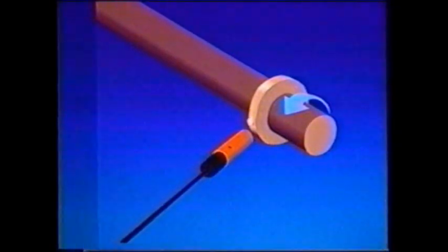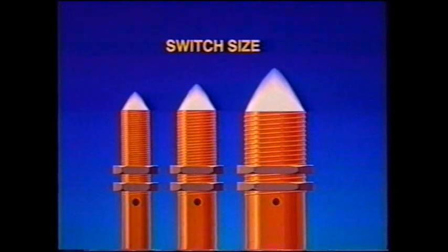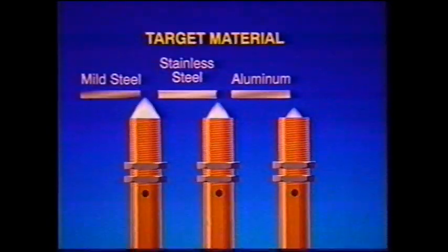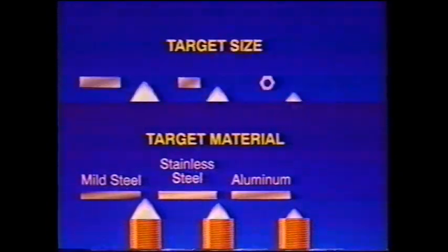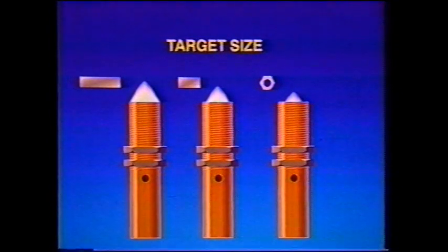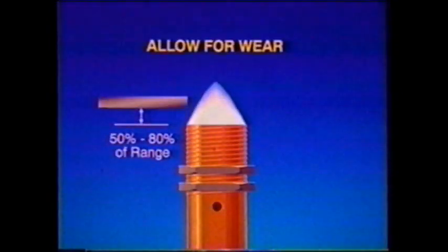To summarize, when you're evaluating the sensing range needed for your application, select a switch that is large enough to provide adequate range. Remember to correct for target material if it is not steel. Try to have a target that is at least as large as the active face of the switch, and operate the switch at about 50% of its actual range in that application.